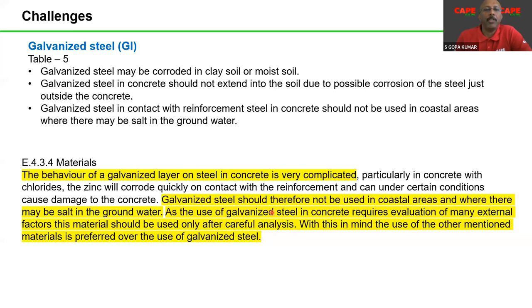So using GI for this purpose inside concrete has to be carried out after careful analysis. But unfortunately, nowhere is it written what careful analysis means. So it is very difficult to find an answer for this careful analysis. The simple method is: don't use it. With this in mind, the use of other mentioned material is preferred over the use of galvanized steel. The standard has recommended very clearly that GI, if you put it inside concrete, has certain problems. Either you analyze and do it if you can, or preferably use the other material over galvanized steel, because galvanized steel is a problem.